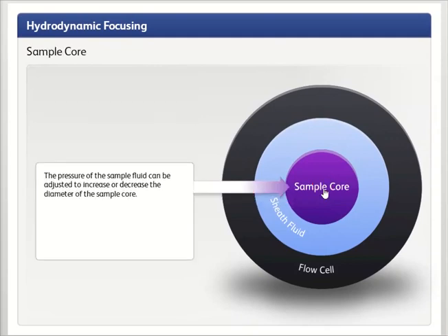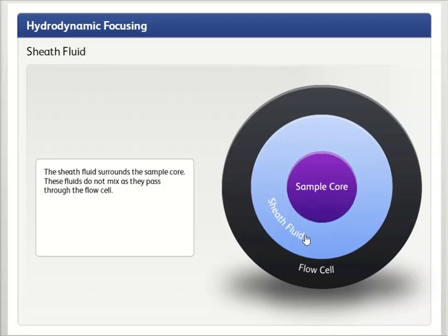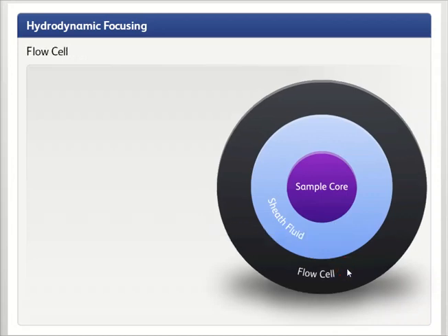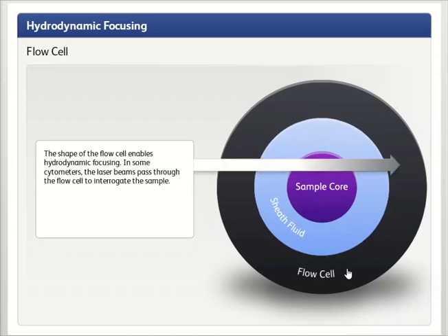The pressure of the sample fluid can be adjusted to increase or decrease the diameter of the sample core. The sheath fluid surrounds the sample core. These fluids do not mix as they pass through the flow cell. The shape of the flow cell enables hydrodynamic focusing.